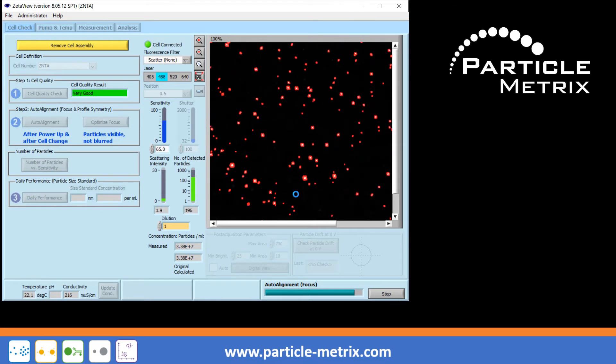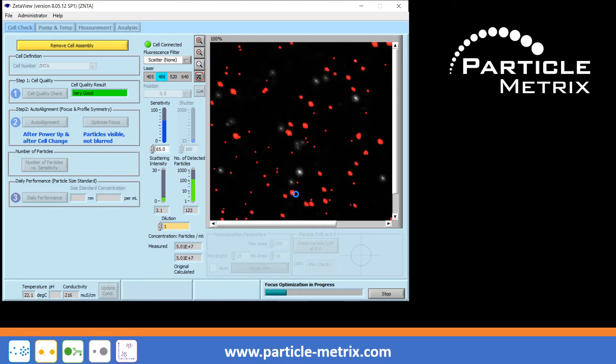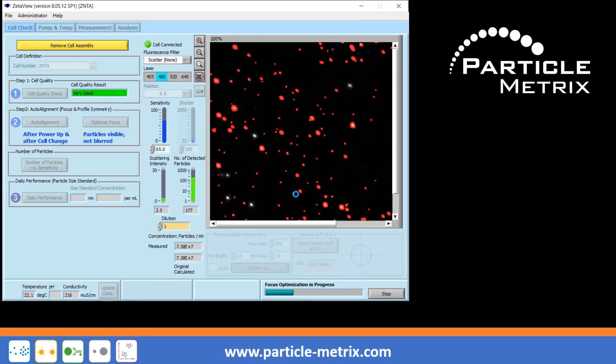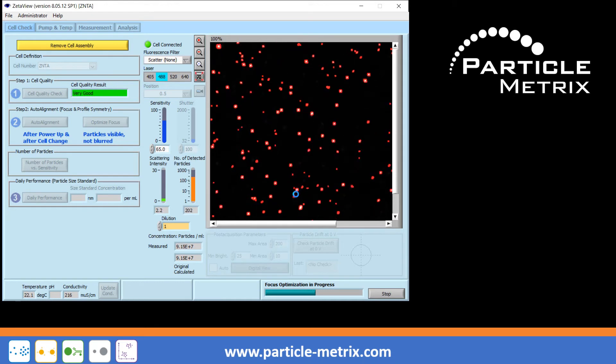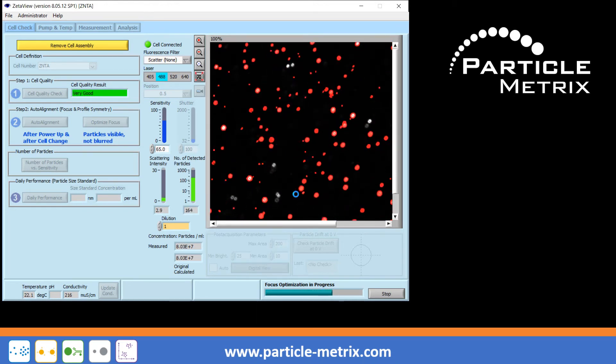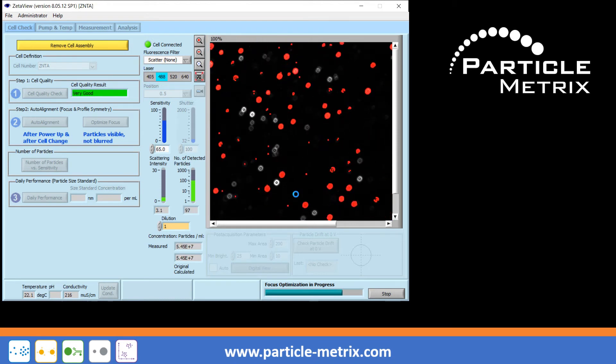The second step represents the focus optimization and takes place in fine increments around the focus point already found in the first step. Depending on the quality of the water in which the particles are suspended or on the age of the alignment suspension, this step can be carried out several times by the instrument.